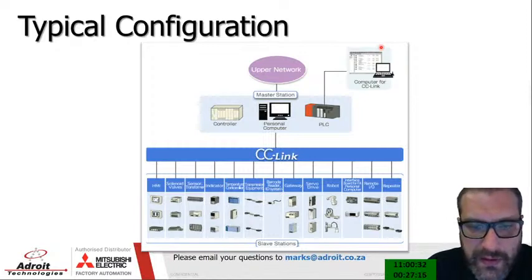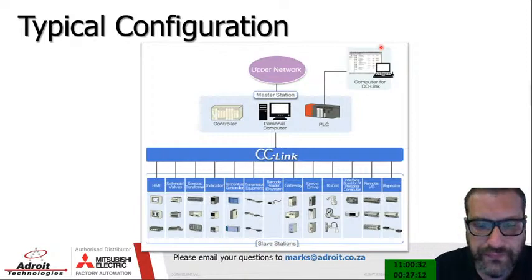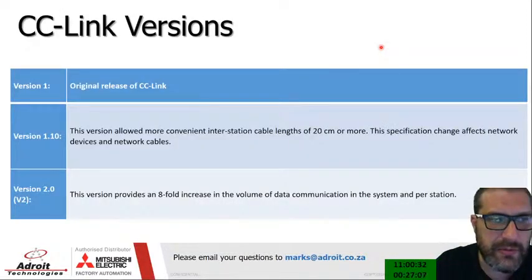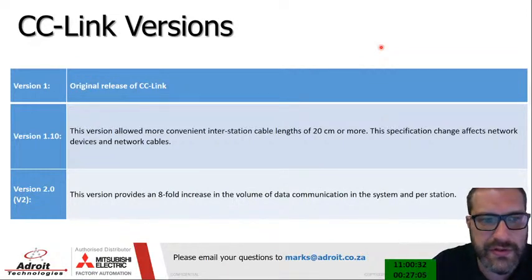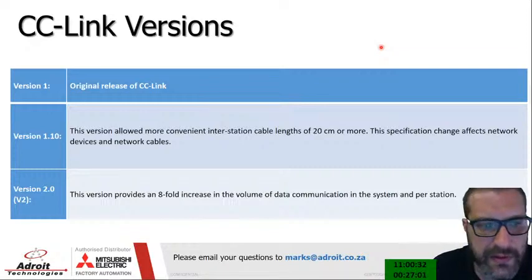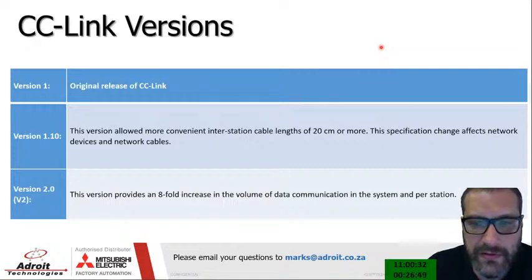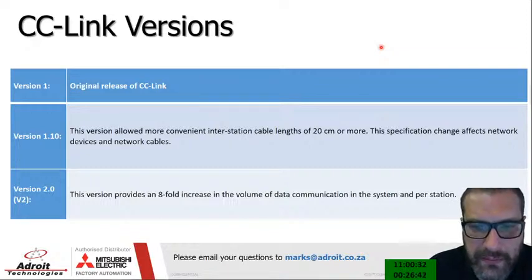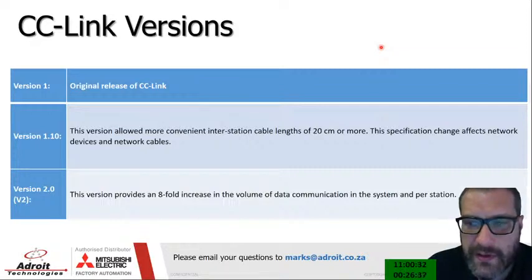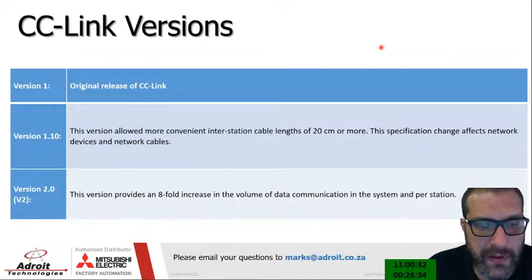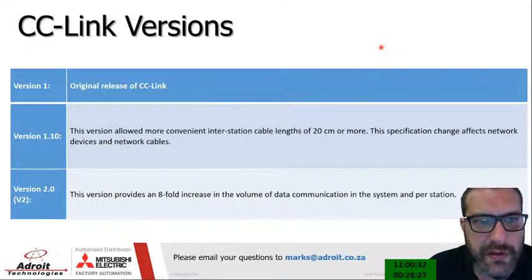There are three versions of CC Link. Version 1 is the original release. Version 1.1 allows more convenient inter-station cable lengths of 20 centimeters or more — so if two stations are next to each other, you need a minimum cable length of 20 centimeters. This specification change affects network devices and cables. Version 2 provides an eightfold increase in the volume of data communications per station, allowing communication with significantly more stations and IO in the field.